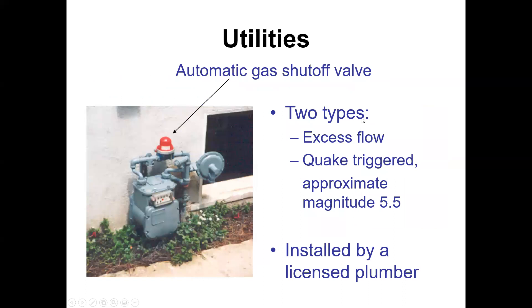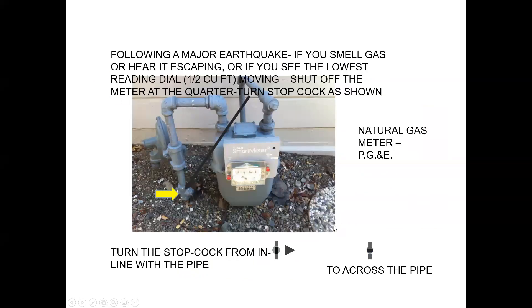Automatic shutoff valves for gas are required if you do any major remodeling. There are two types: excess flow and quake-triggered, triggered at approximately magnitude 5.5. They can be installed by a licensed plumber for about $400. Following an earthquake, if you smell gas, hear it escaping, or see the lowest reading dial moving, shut off the meter at the quarter-turn stopcock — turning it from in-line with the pipe to across the pipe.